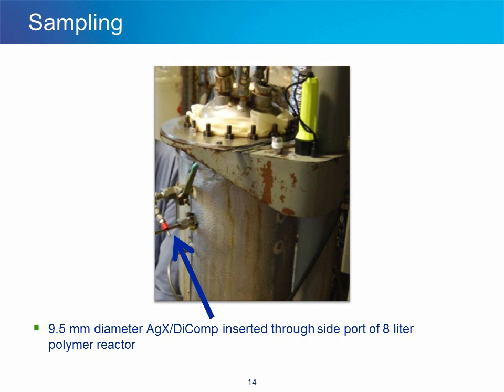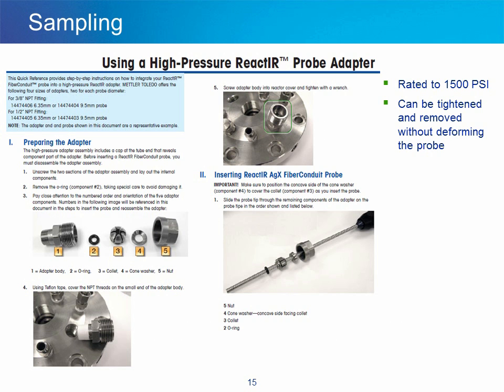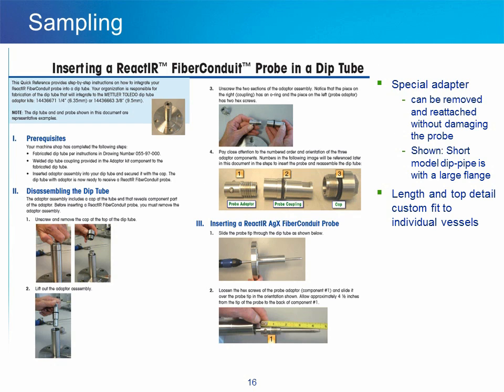This is an example of a 9.5 millimeter diameter silver halide diamond probe inserted through a side port of an 8 liter polymer reactor, using a high-pressure React-IR probe adapter. This adapter is rated to 1500 psi and is designed so that it can be tightened and removed as many times as desired without deforming the probe body. For this reason, we recommend this adapter as opposed to a conventional compression fitting. In order to secure a silver halide probe in a dip pipe, a special adapter is used that can also be removed and reattached without damaging the probe's metal wall. A short model dip pipe is shown with a large flange, and in practice the length and detail at the top of the dip pipe will be custom designed to fit individual vessels.